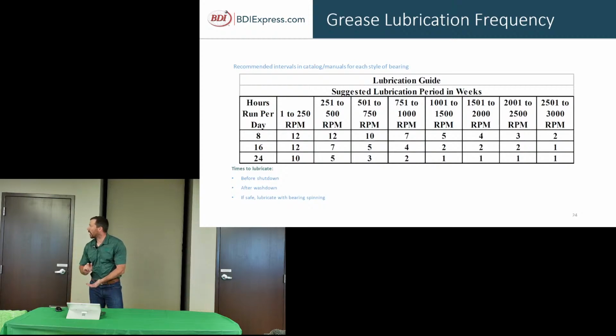And then as for mounted bearing greasing, lubrications, anybody use auto greasers or lube lines? So if you have a greaser mounted outside of an air handling unit. So yeah, there's those applications. Since you have that long travel distance, it's best to consult. You can get with Josh. We can get with a Dodge engineer or some engineer to tell us, if you're at 5 feet, how many pumps you need to get in there, whether it's a fresh line that you just installed or an existing one. But it's going to be measured off of your runtime, your RPM, and also your shaft length and shaft diameter.